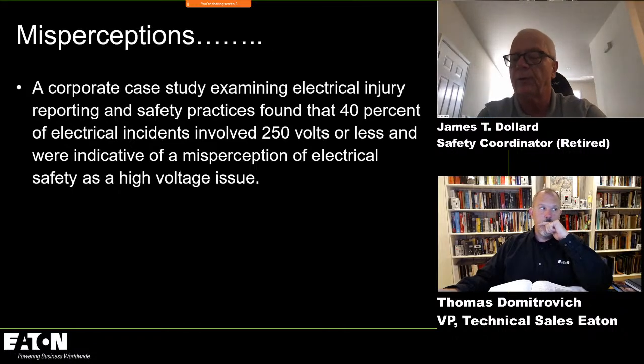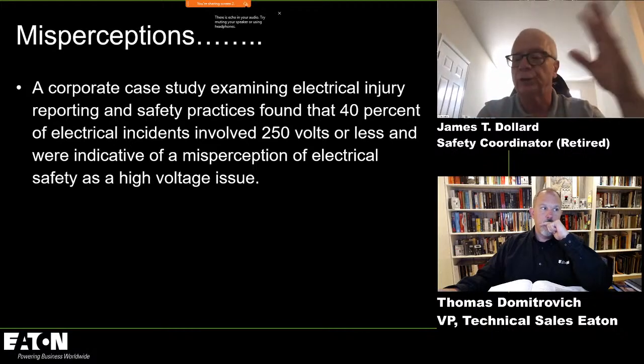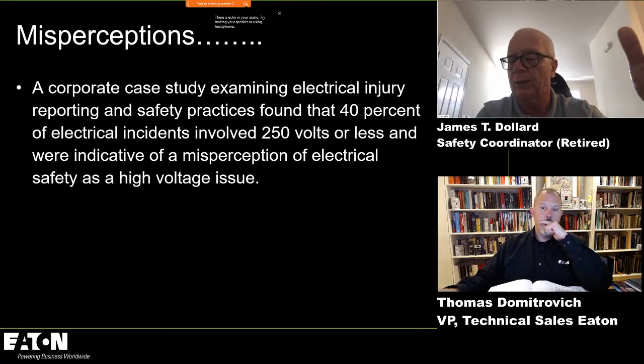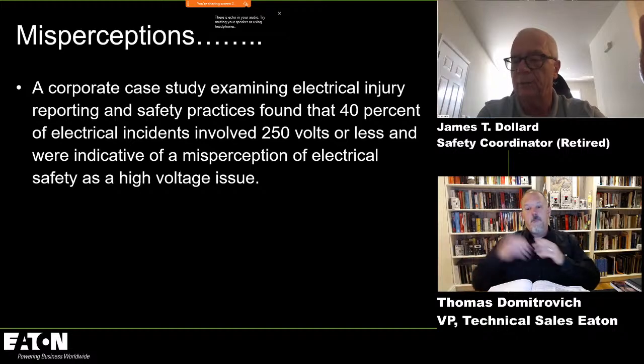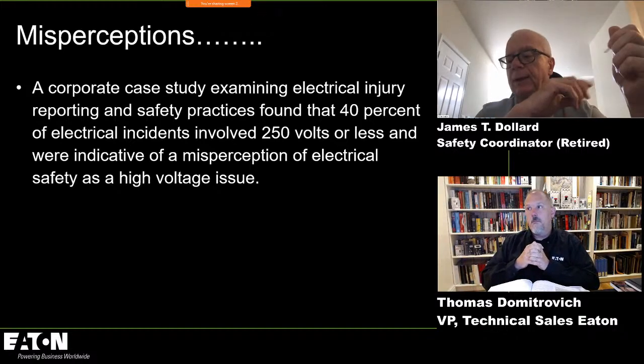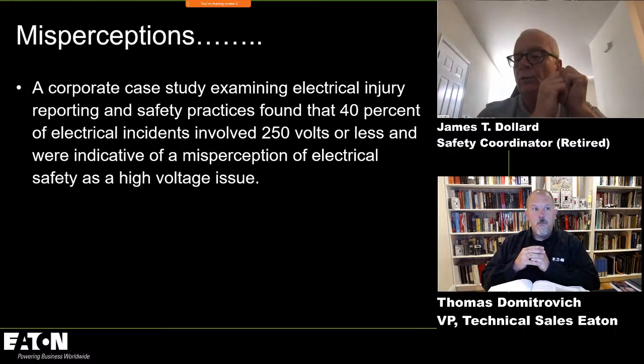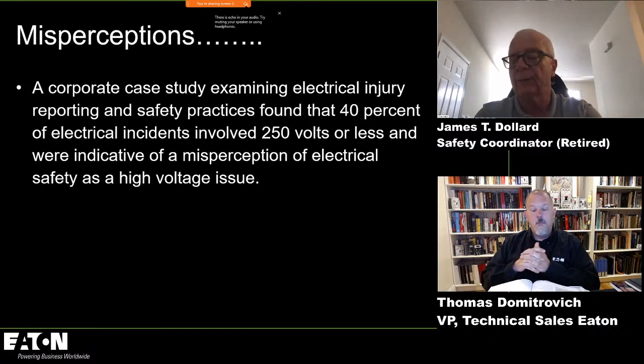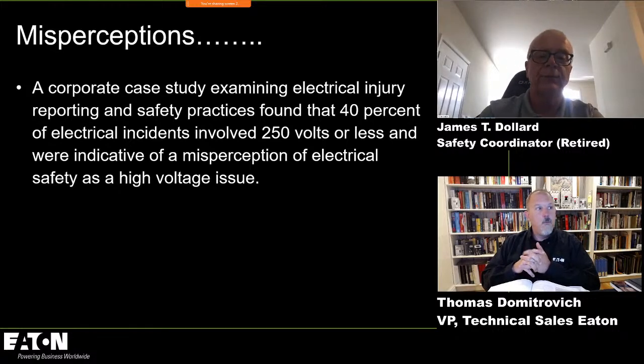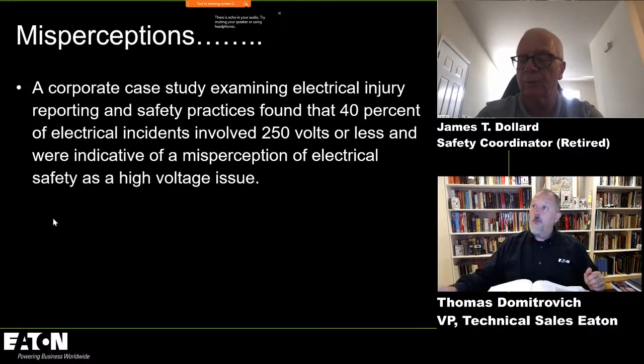For example, under the right conditions, it's July. You're sweating. Your jeans are wet. You're on wet concrete. You're kneeling down. Yeah. You're dealing with energized conductors, and you get an equipment grounding conductor in your left hand and an ungrounded conductor in your right hand. You get to the let go threshold. You fall into the wall. Typically, when somebody gets a shock like that and hung up, they're on a ladder, and gravity is the method of release. But if you're kneeling and you fall into something, there is no method of release. So, the misperception piece is that electrical workers believe that 277, for example, is far more dangerous than 120. It has nothing to do with the voltage. It has to do with current flow through the body.